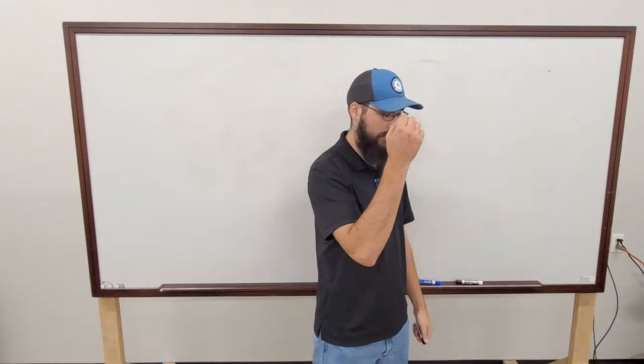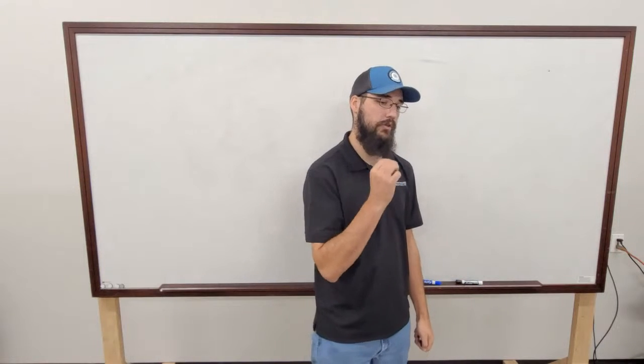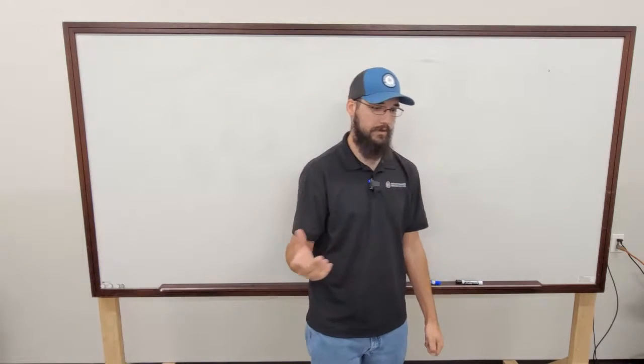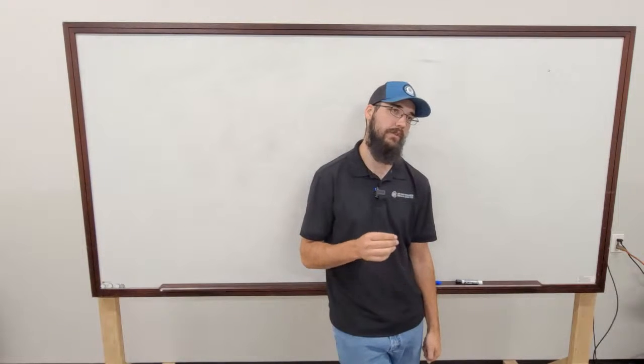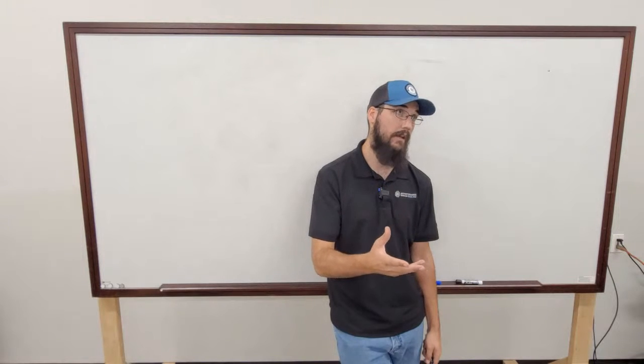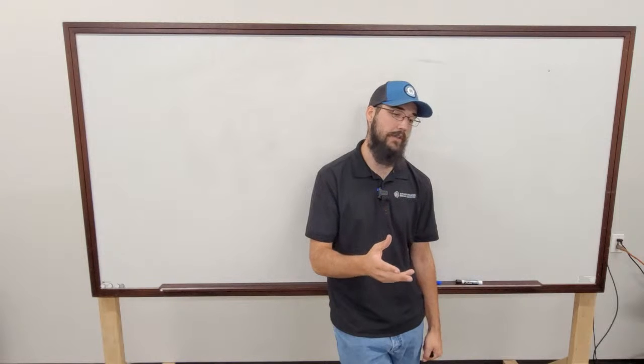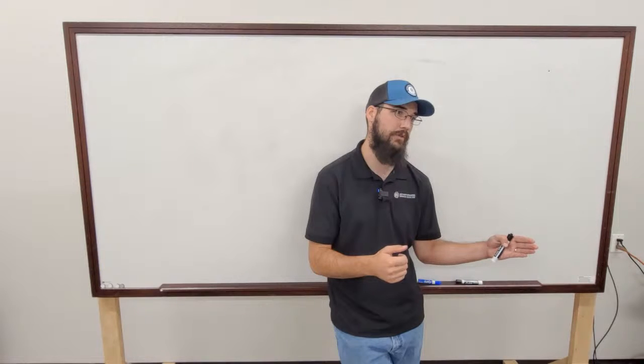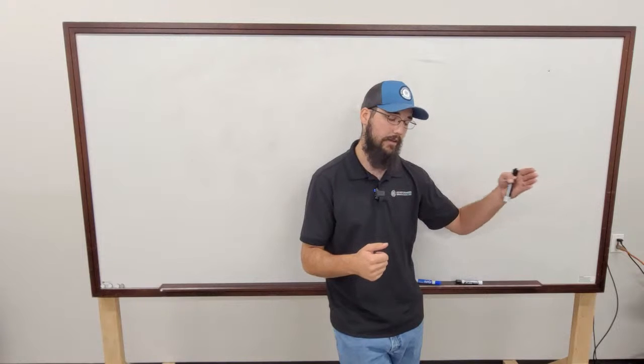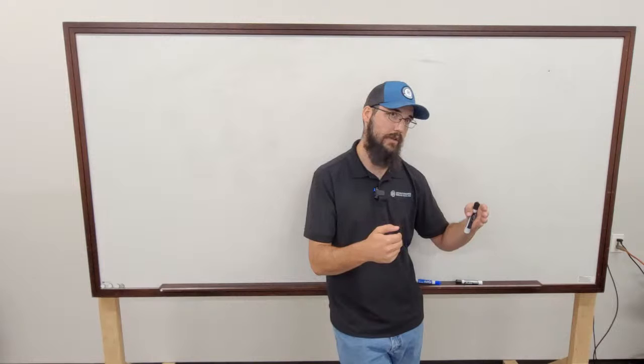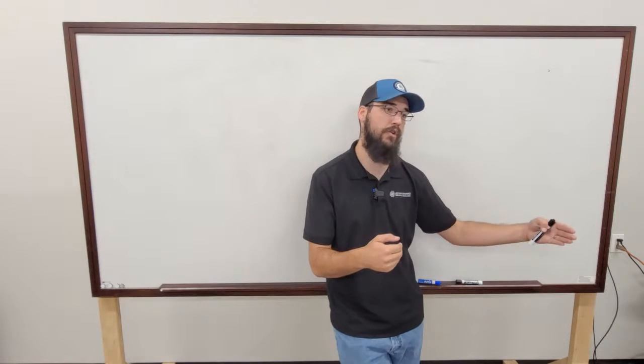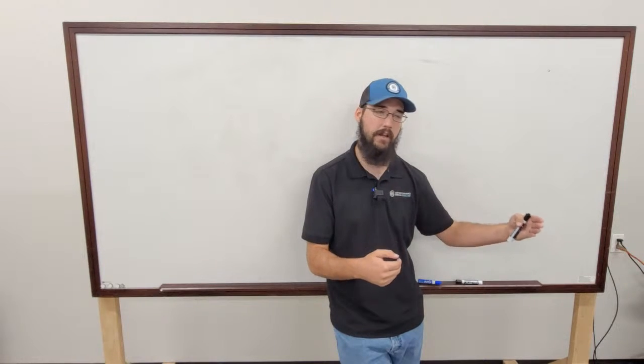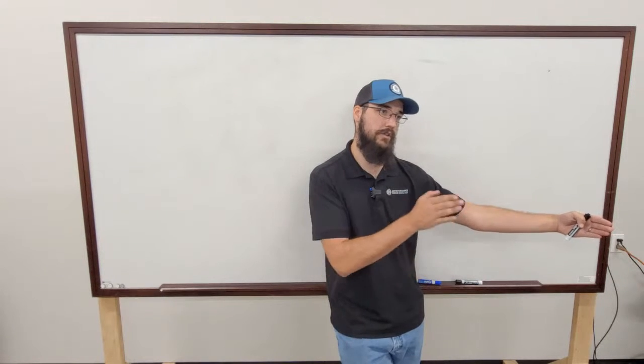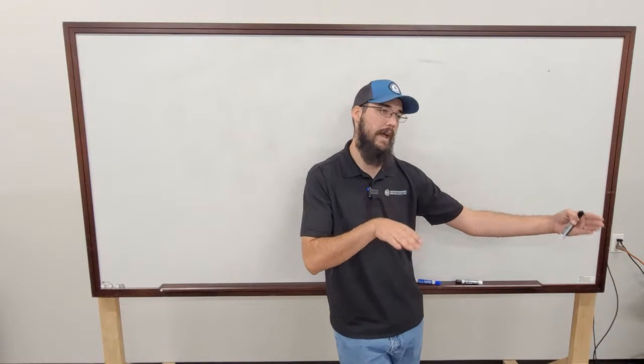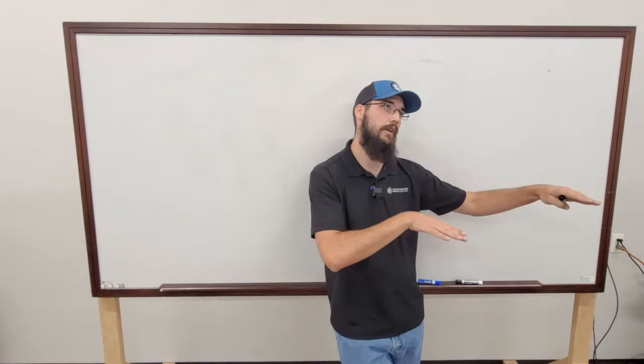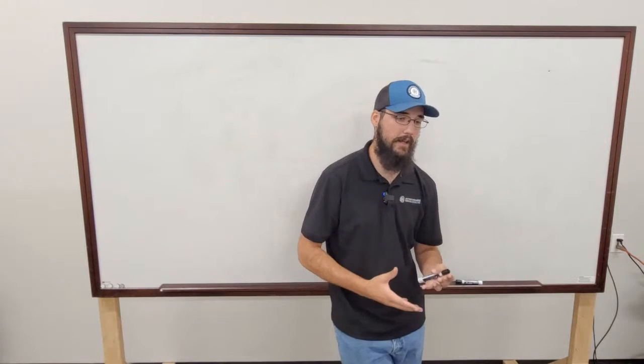Now, yes, scrolls that are on drives, obviously they have the ability to better tune that. And that is technology that we're seeing more and more of. So what I'm specifically speaking towards is machines that don't have that capacity. But even in a machine that has a variable speed scroll, that's usually the lead or the first two compressors. And so you could have a 4-bank circuit, and 1 and 2 may need to fully stage, but by themselves, they still need that third one, that in-between point. Now, I know some of the logics can get kind of crazy to where it'll stage 3 on, shut 2 down, and it can then ramp 1 to match, or ramp 2 to leave 1 at 100%, 3 on, and then 2 can then match load, and they can do that kind of stuff.